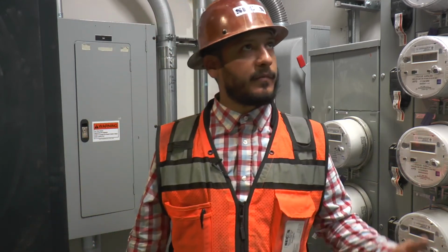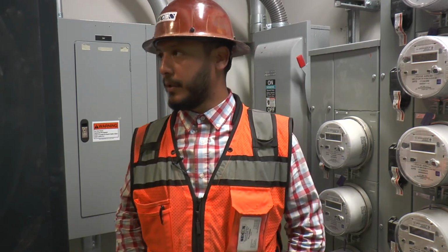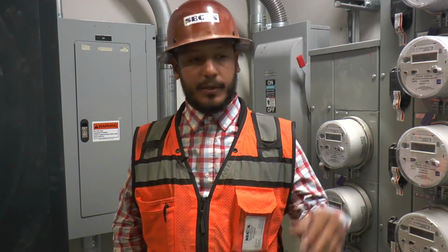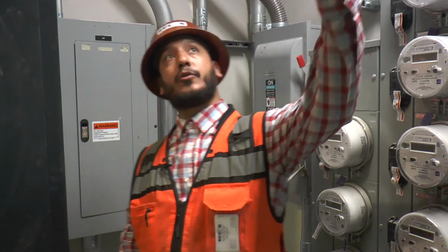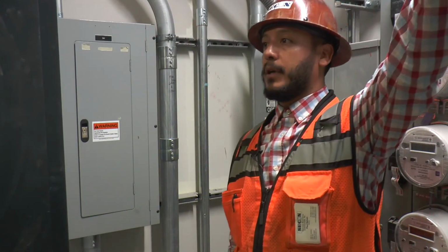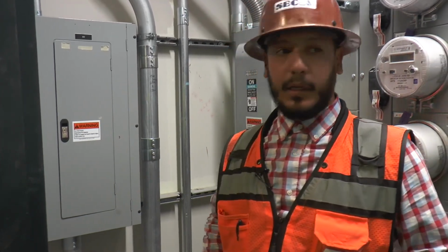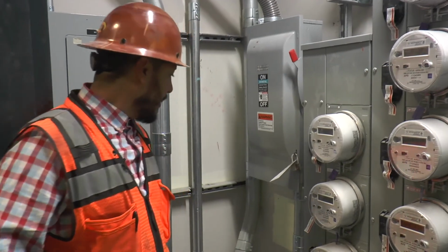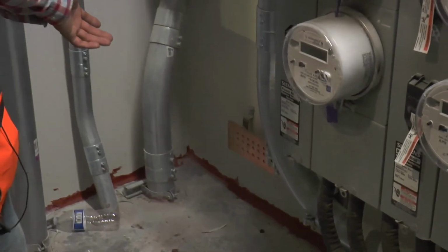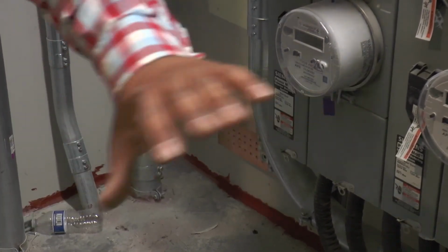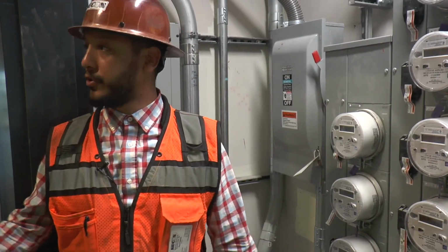Then when you get up to level 12, you'll have another high volt panel as well, a tap to a transformer, and that'll be your emergency power, which controls these boosters that we have on each floor. All of this fire alarm has to pertain to all the emergency egress. You also have grounding. If anything is to be added, you have your grounding purpose here for all equipment. All this is protected by our grounding rod farm that is directly located in our electric room.